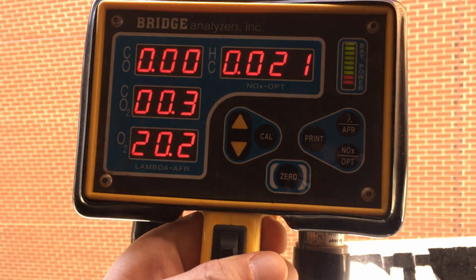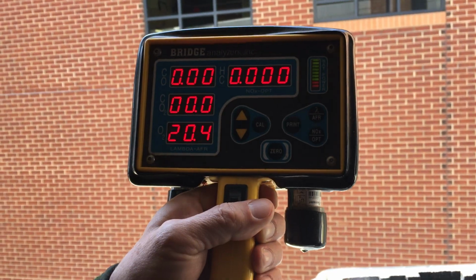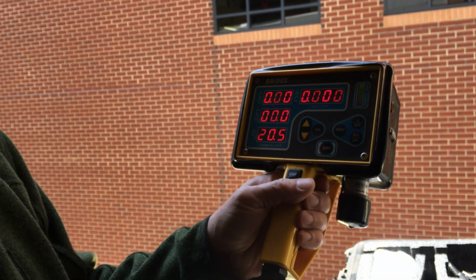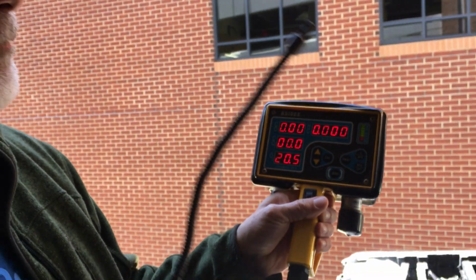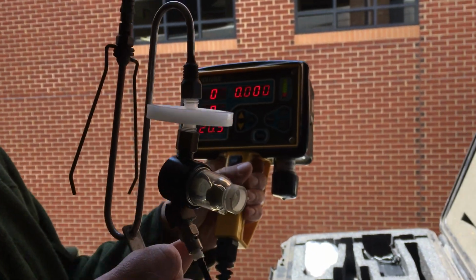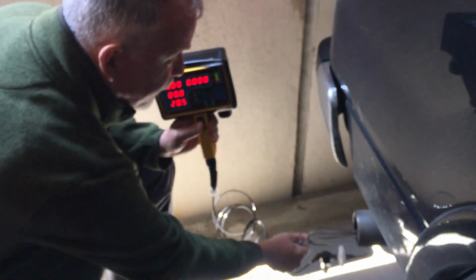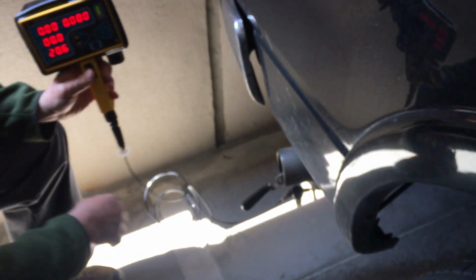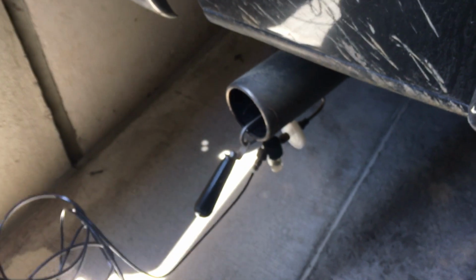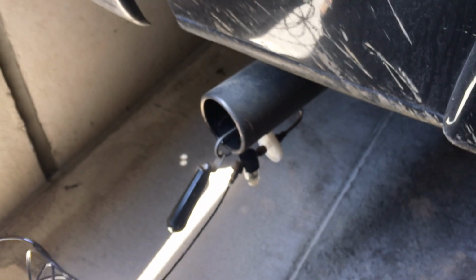Okay, so we're here in the parking deck at Virginia Tech, and you can see we're calibrated, 20.5% oxygen. Everything is zeroed out. I'm going to go ahead and put the probe in the exhaust of my F-150. I can put it in all the way through, and I'm just going to let it lay there for a minute, and we'll see how it responds.